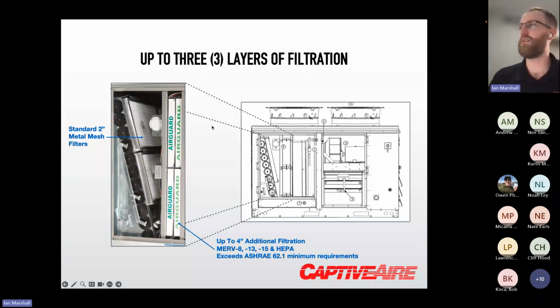So this is a good cutout of the unit to see the airflow configuration. The outdoor air would be coming in from the left side through the filtration here, and then into the evap coil, into the blower cabinet, discharge down into the heater cabinet, and then either down to the base or out through the side of the unit towards us, as the general airflow path. And then if there was return air, that return air would be coming up through the base here and mixing with that outdoor air to be brought back towards that evap coil there.